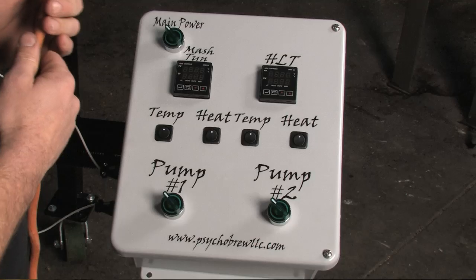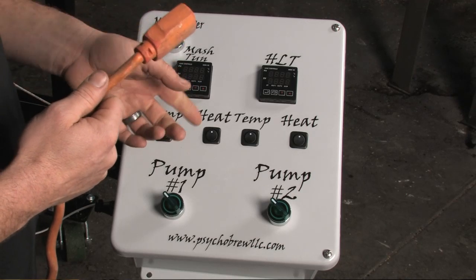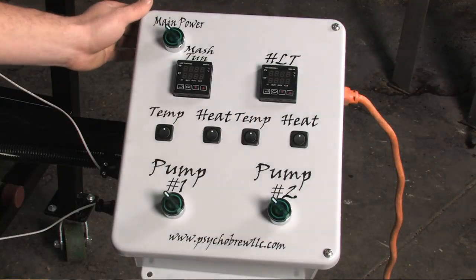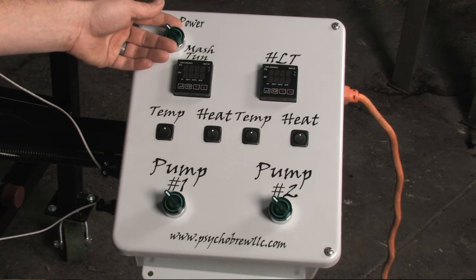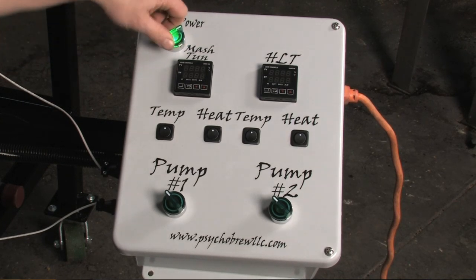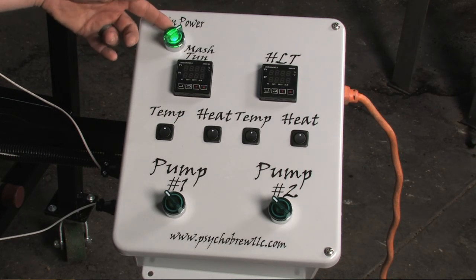Now for some of the technical aspects of the controller for startup, to alleviate some of your nuisance problems. First of all, you want to plug it into a 120 volt grounded circuit, GFI preferably. 3-prong has to have a ground plug, and the cord itself also has to have a ground wire. This is important for flame rectification, for improving flame for the burners, and also for GFI circuits inside the panel. After you're hooked up, you've got a main power switch which kills power to the whole panel. Flip that on. Green light, you're ready to go.